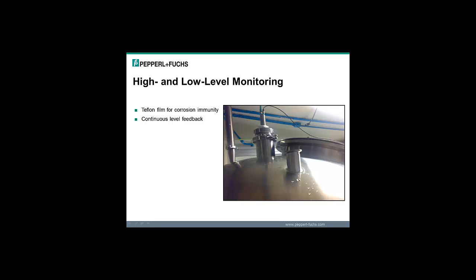I think the quintessential application for ultrasonic sensors is level control. So you see that in small tanks, big tanks, corn to beer to whatever. This particular tank was a little bit caustic on the inside, so they wanted a Teflon film. So this sensor had a Teflon film, one of our UC2000 sensors, and gave the customer continuous level feedback, and it's fitted into a flange that goes into the top of the tank.